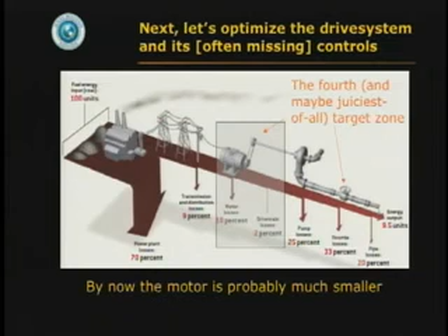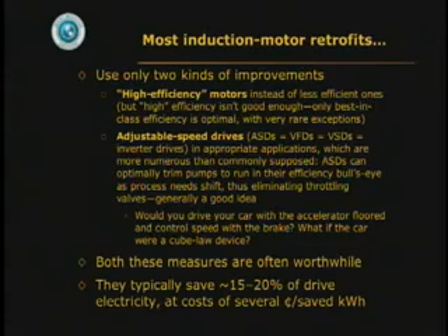Now, maybe the juiciest of all target zones is the motor systems and controls. And normally when you talk to retrofitters, they say, well, we'll put in high efficiency motors. Not a very meaningful term. Only the best in class efficiency actually is optimal in most cases. And they put in these adjustable speed drives which let the motor go faster or slower. And that has a lot of good uses in most applications. It's often a good idea, even if your load isn't changing much. You know, would you drive your car with the accelerator on the floor and just control speed with the brake? And what if the car were a cube law device? You certainly wouldn't do that. So both these things are often worthwhile, and they'll typically save you about 15 or 20% of your drive system electricity, and they'll cost a few cents per saved kilowatt hour.